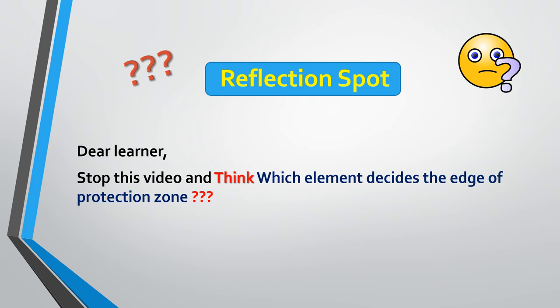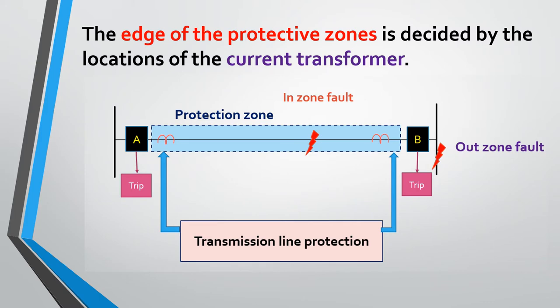Stop the video and think: which element decides the boundary of protection zones? You are now familiar with the term protection zone and the concept of blind spot or dead spot. The boundary of the protective zones is decided by the location of the current transformer.